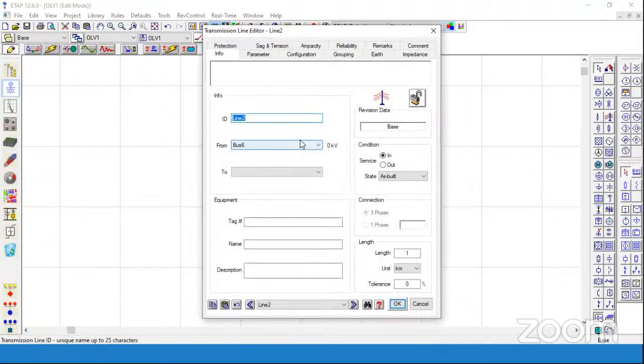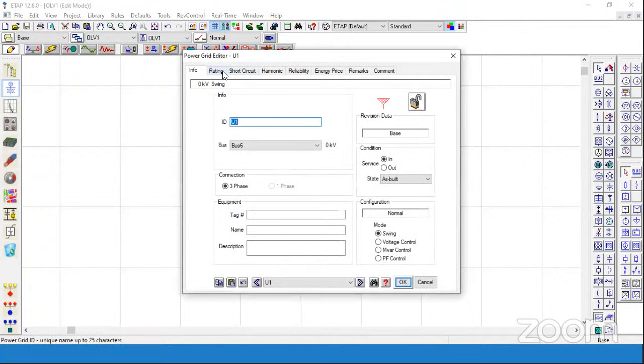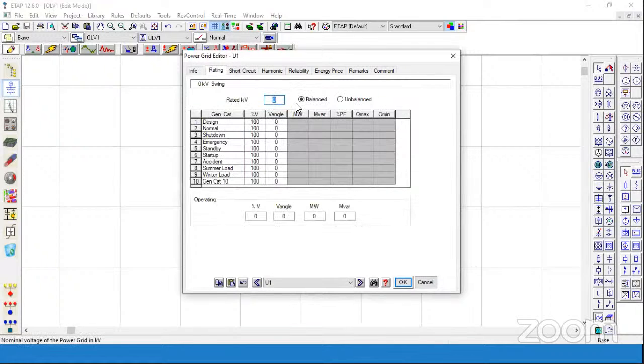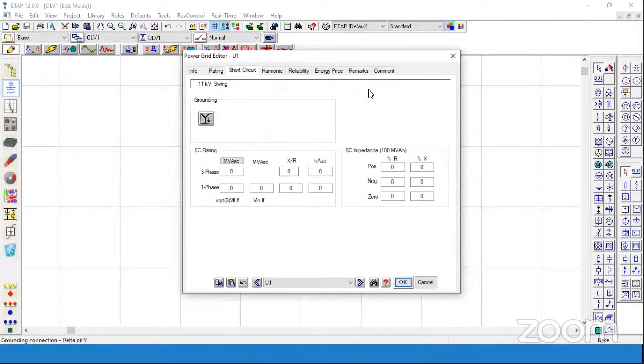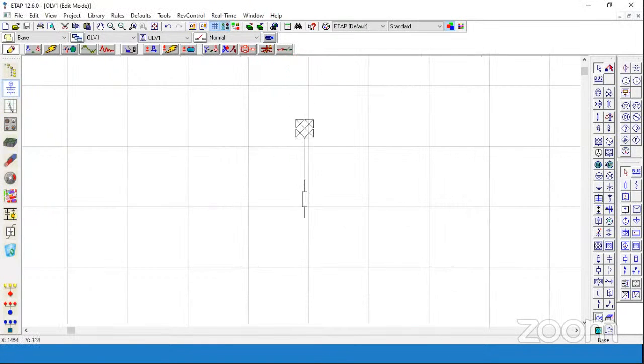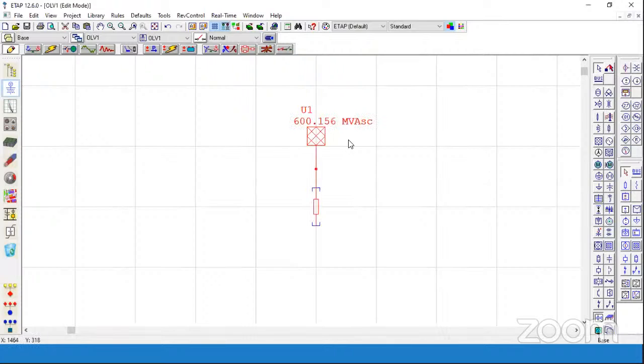Here we can define the voltage level for the grid, at what voltage level we are modeling the system. For rated kV, we are modeling an 11 kV system right now. For the short circuit parameter, we need the system fault current details. If we don't have them, we can ask the utility, that is, our generation, transmission or distribution company, who have these parameters. For example, I am taking 31.5 kA as the fault current, so I am modeling this 11 kV grid with a maximum fault current of 31.5 kA.